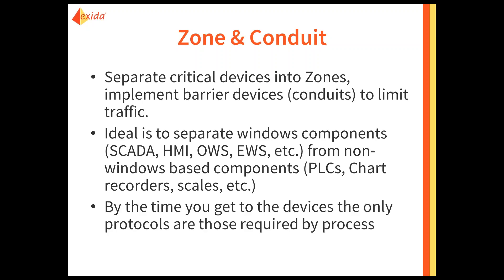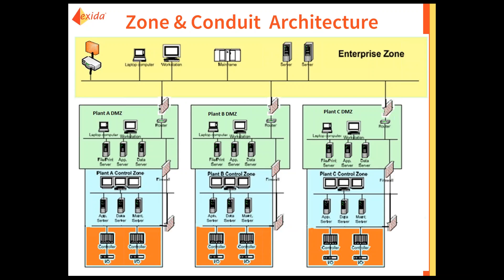The whole goal of network segmentation is that by the time you get to these end devices, only the protocols required to run those devices should get to them — and that's what the firewalling is doing. Here we've taken our original architecture, reviewed what needs to happen, and developed a zoning conduit architecture. At the top we have our connection to the internet, which is routed and firewalled. We have our desktop enterprise stations, and a firewall and router creating an isolated but dedicated connection to three plant DMZs.